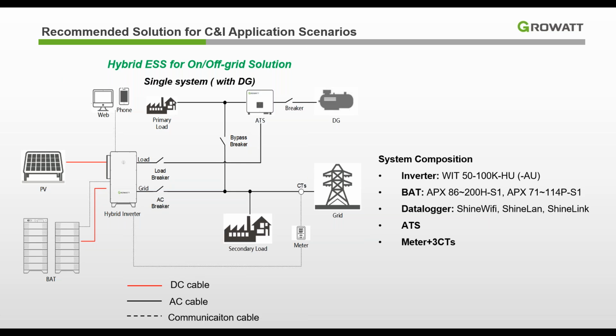And here, when the inverters receive a signal from the battery that tells you the SOC is low and you can't use it anymore, then the generator will kick in by the automatic switch, the ATS, and this can either feed your load or charge your batteries. But the wiring would be different if you want to use the generator to charge your battery.